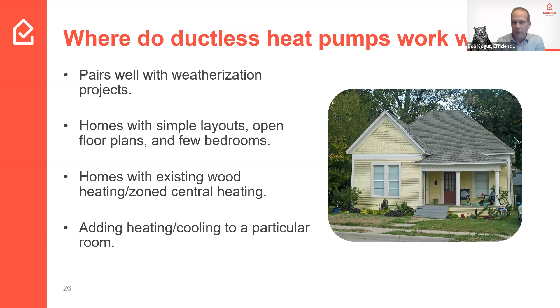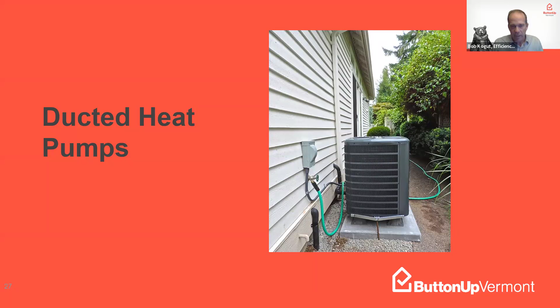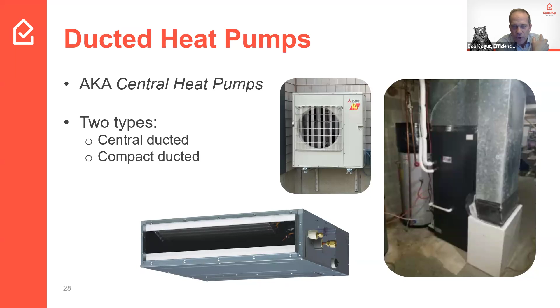Now, ducted heat pumps. A ducted heat pump uses the same technology, with an outdoor unit and an indoor unit as we've said before, coupled with a duct system in your house to move heat around. There are a couple of different types. A central ducted system is just like a forced hot air furnace you might already have, and heat pumps can generally use the same duct distribution system as your current furnace without requiring different designs. That's something to talk to your contractor about. If your house already has duct distribution in good shape, you can reuse that, and a heat pump can be engineered and designed to hook up to that system.